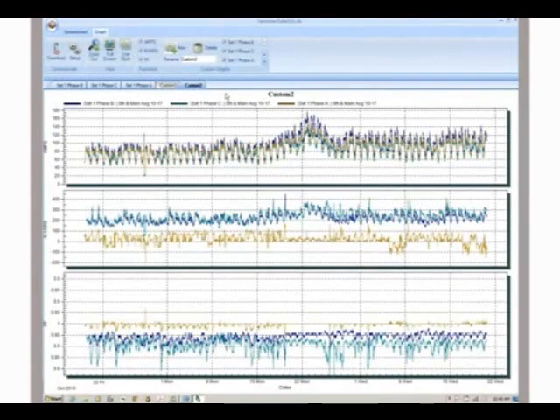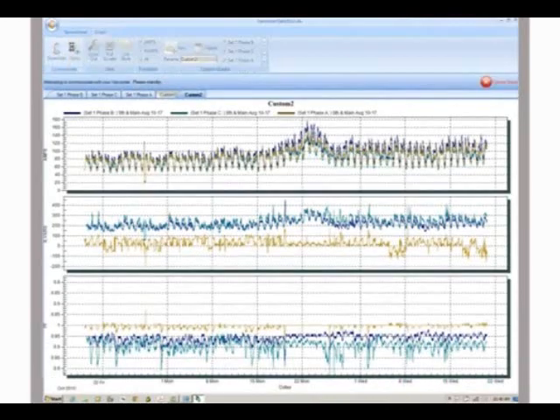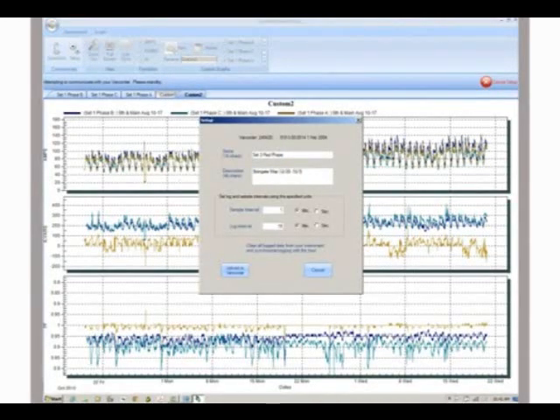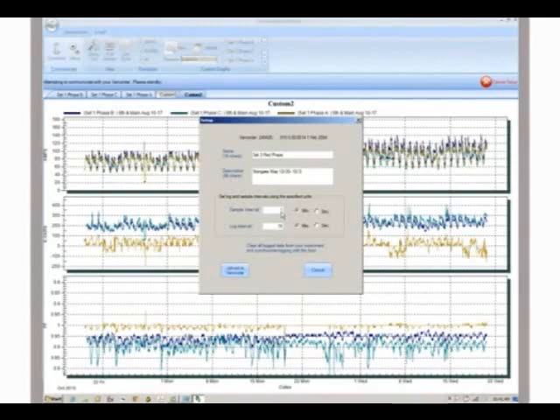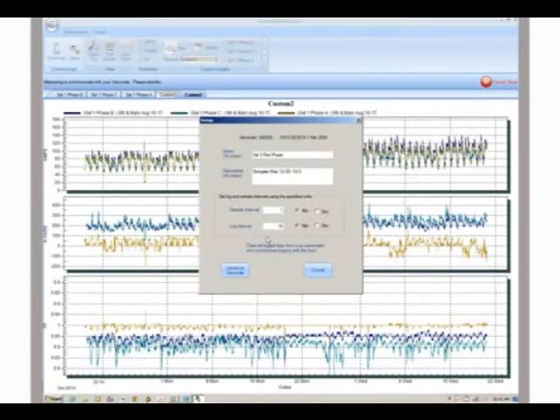Before redeploying your recorders, you may want to change their setup parameters. To do this, select the setup icon from the toolbar. Here you can change the name and description of the recorder. You can also set the sample interval to determine how often the recorder samples the line, and the log interval to determine how often the recorder stores the average of the samples.